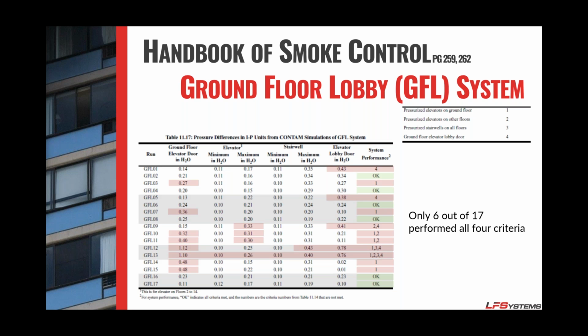Okay, the first one had over 0.4 inch pressure, even with a vent at the lobby door. Which means that, while the lobby doors swing out, that pressure would push those doors open to where you're no longer able to pressurize that space. Simulation number 13 fails all 4. So if that's your building, you definitely wouldn't consider the ground floor lobby in that scenario.